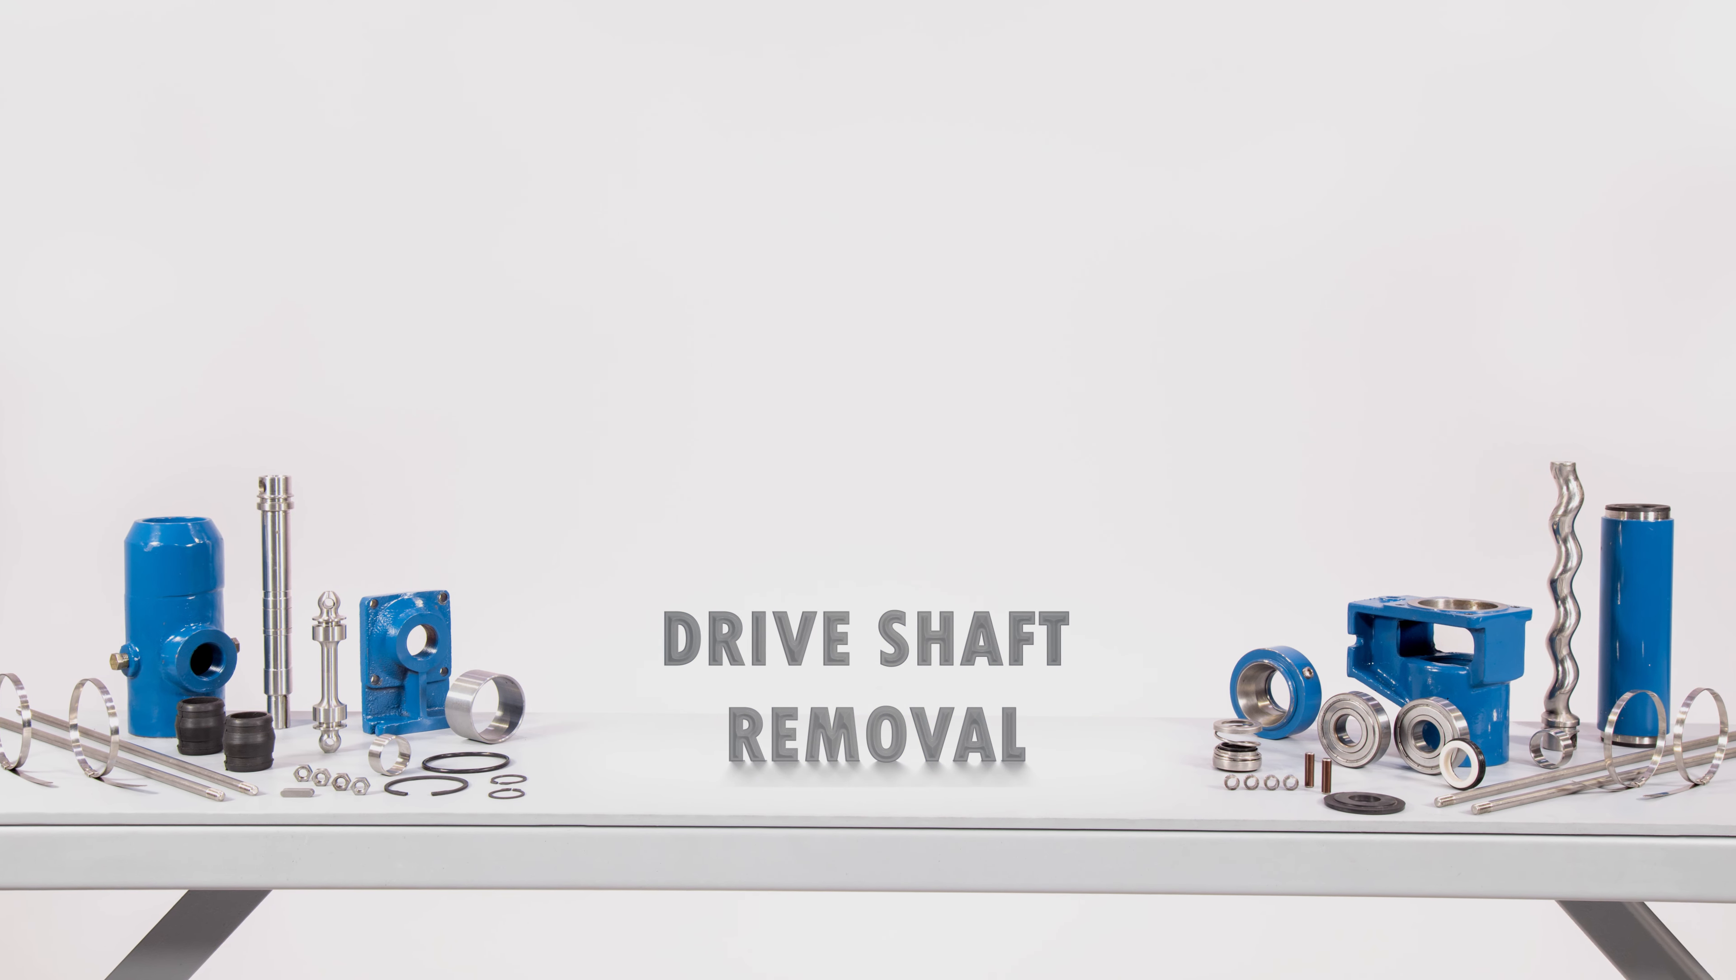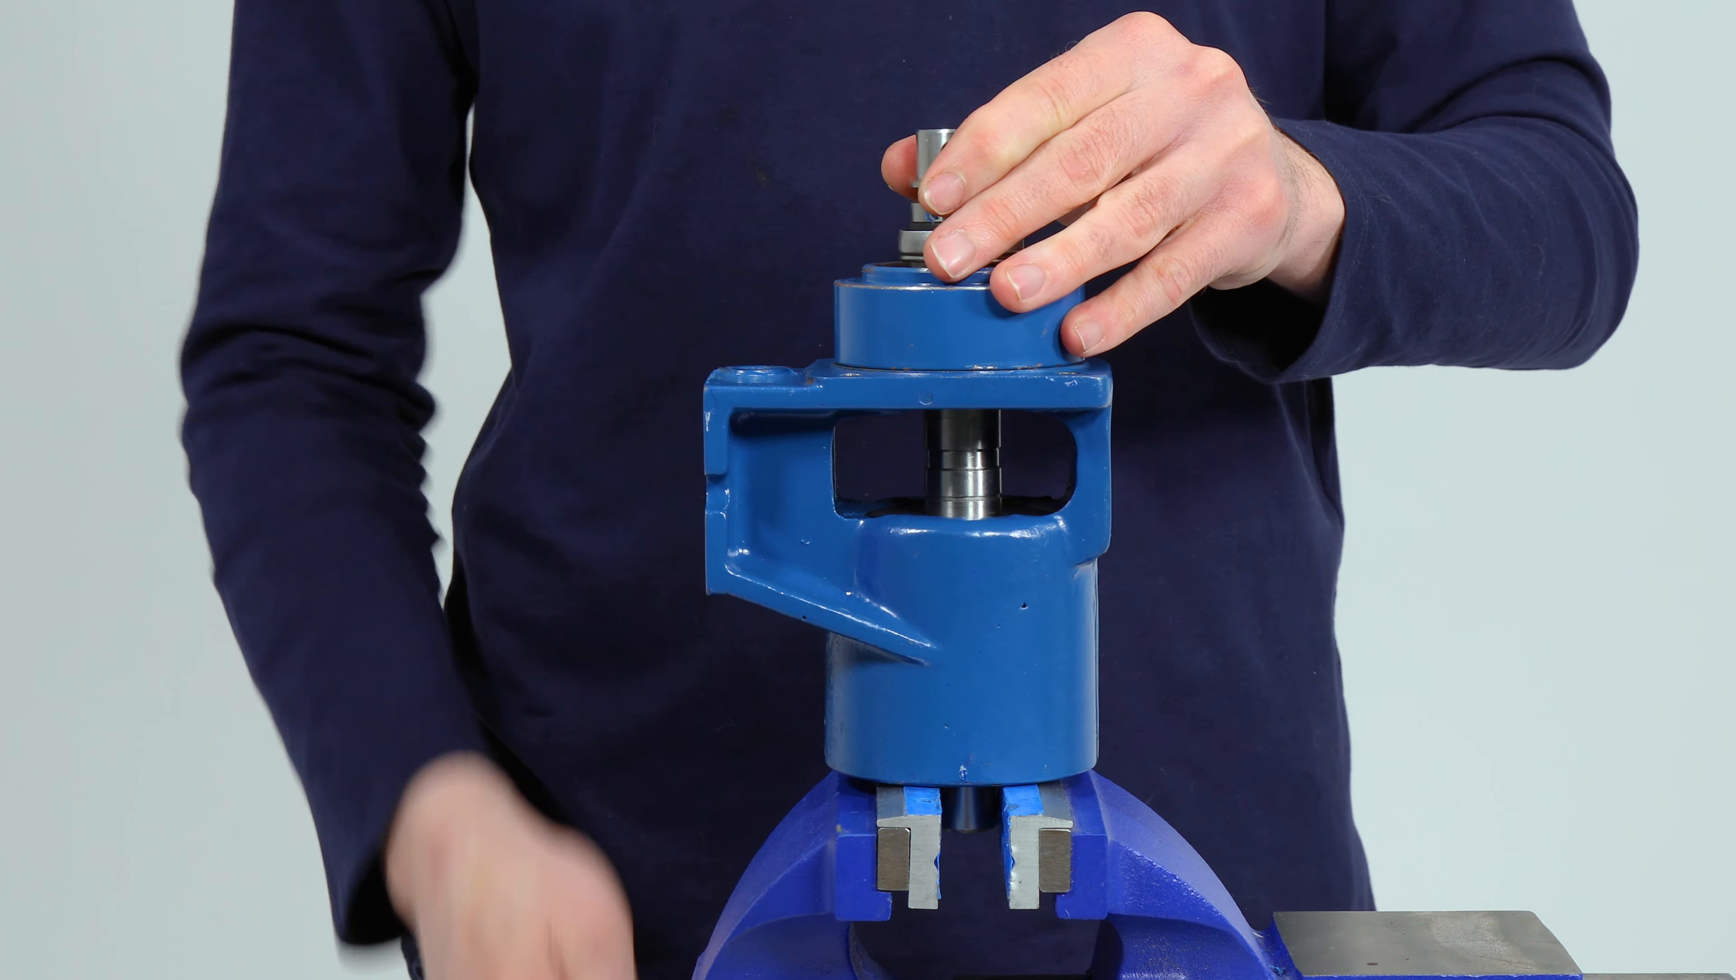Drive shaft removal. Flip the bearing housing vertically in the vise and secure at the drive shaft head. Remove the key from the keyway using a hammer and punch. Once again, flip the bearing housing vertically and secure at the keyway.